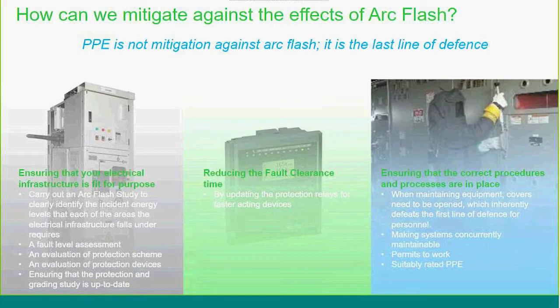I've been auditing power systems for 30 years, and sometimes I know when something's not right. We all know when something's not right if we're electrical engineers. There's a strange smell or a strange hum in the substation, a strange noise. Well, that's good, but it's not as good as understanding exactly what the energies are that you might be faced with in that substation should that equipment fail.